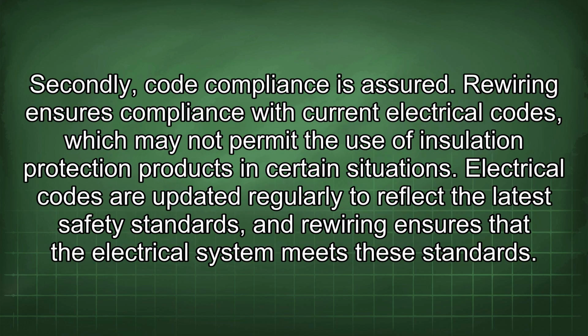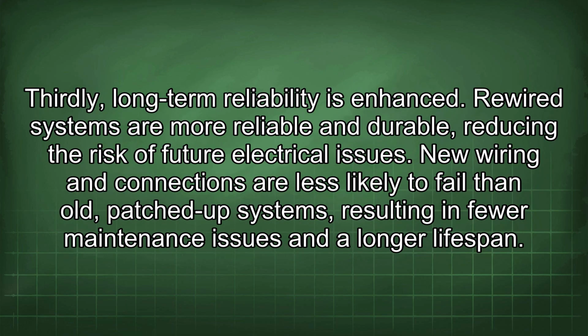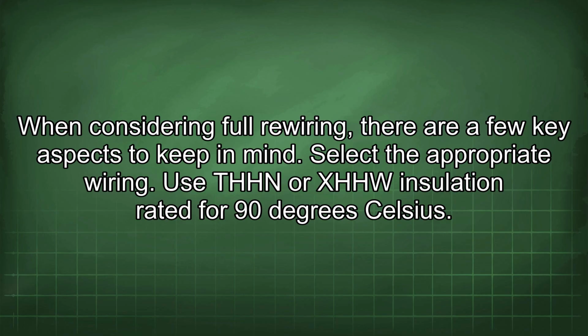Secondly, code compliance is assured. Rewiring ensures compliance with current electrical codes, which may not permit the use of insulation protection products in certain situations. Electrical codes are updated regularly to reflect the latest safety standards, and rewiring ensures that the electrical system meets these standards. Thirdly, long-term reliability is enhanced. Rewired systems are more reliable and durable, reducing the risk of future electrical issues. New wiring and connections are less likely to fail than old, patched-up systems, resulting in fewer maintenance issues and a longer lifespan. When considering full rewiring, there are a few key aspects to keep in mind.